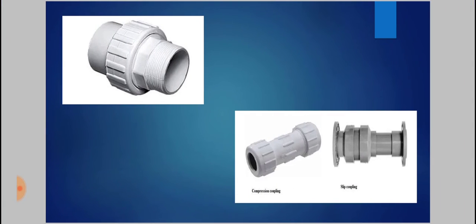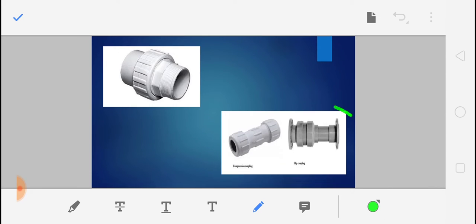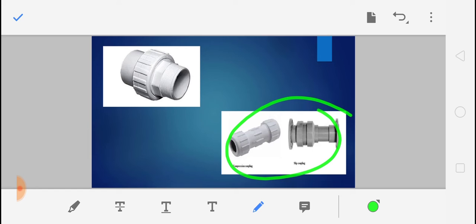The next fitting is the coupling. A coupling is used to connect pipes of the same diameter and is used when a pipe is broken or leakage occurs. There are two types of couplings: compression coupling and slip coupling. A compression coupling is connected between two pipes and prevents leakage by using gaskets or rubber seals on both sides or by glue. A slip coupling is easier to install and contains two pipes arranged one inside the other; the inner pipe can slide up to some length, so it can be used to fix long lengths of damaged pipe.